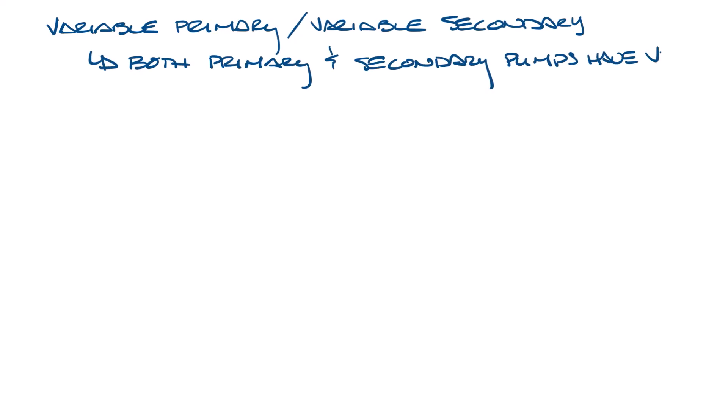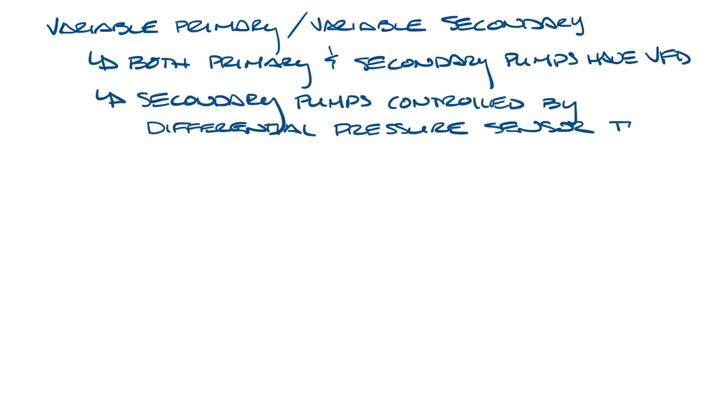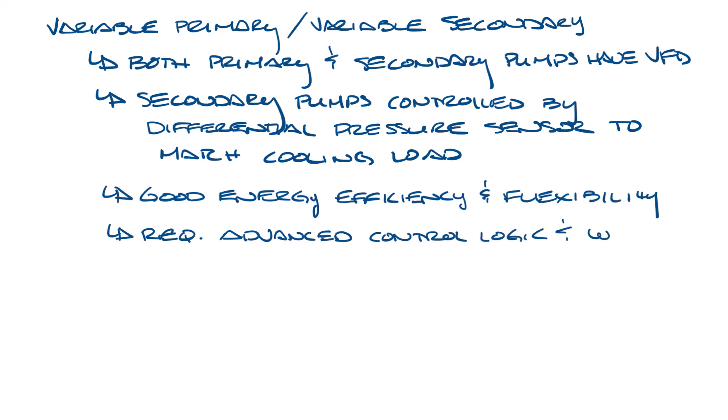Let's move this up one more time. Then we have the variable primary variable secondary system. In this system, both the primary and secondary pumps have a VFD to vary the flow. The secondary pumps are controlled by a differential pressure sensor to match the cooling load. These systems have good energy efficiency and flexibility, but they do require advanced control logic and well-placed sensors to make it all work correctly.